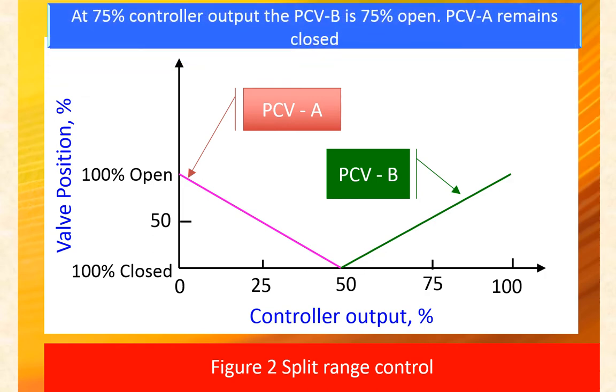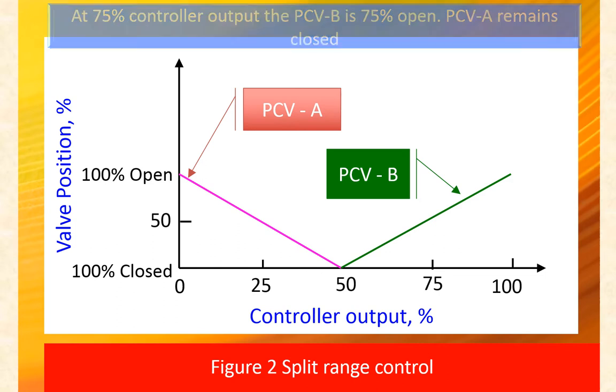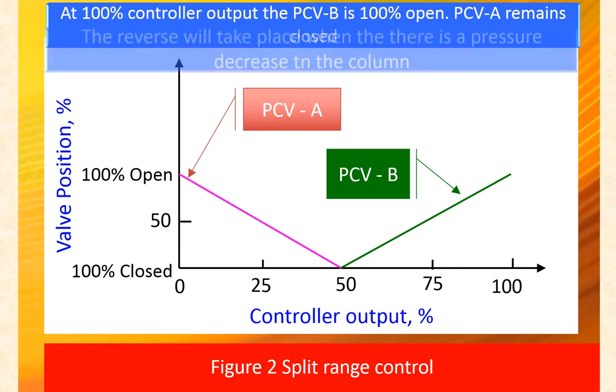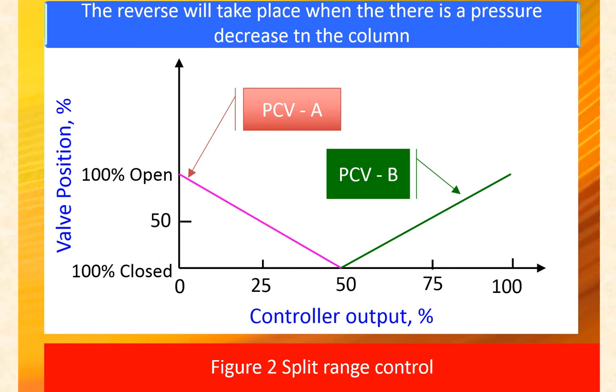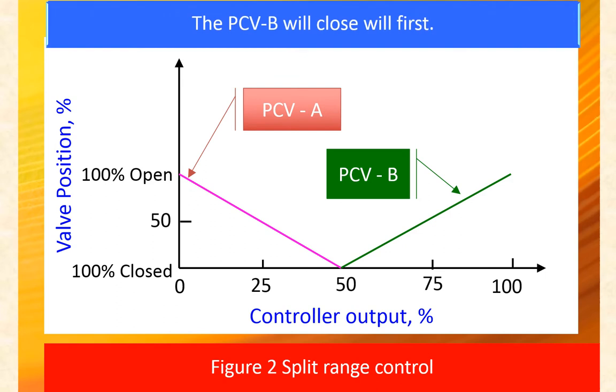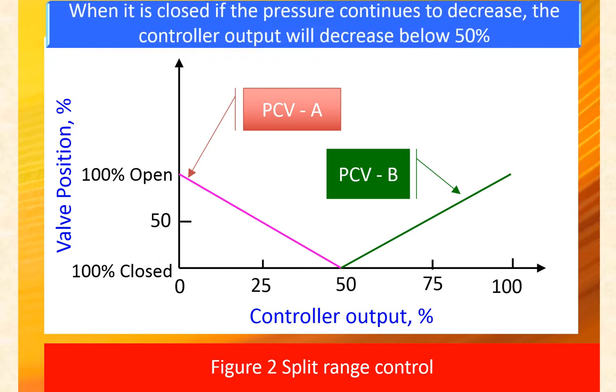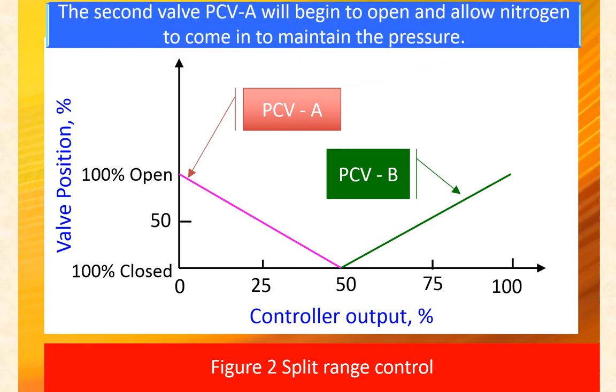As the output increases beyond 50%, PCVB starts opening. At a controller output of 75%, PCVB is 50% open. The reverse takes place when there is a pressure decrease in the column. PCVB will close first, and if pressure continues to decrease, the controller output will decrease below 50%, and the nitrogen valve PCVA will begin to open and allow nitrogen to come in to maintain the pressure.